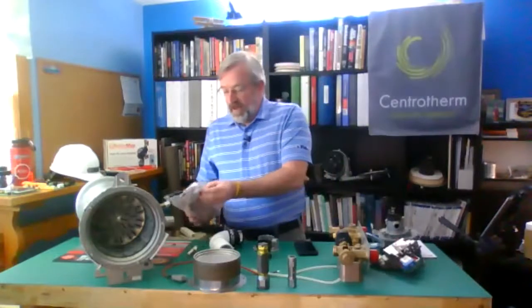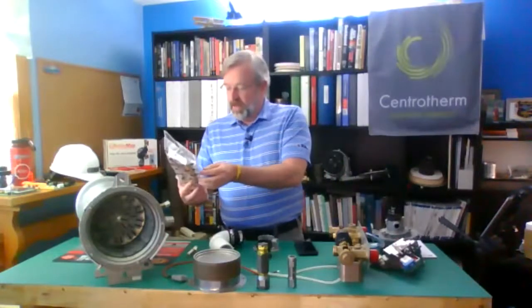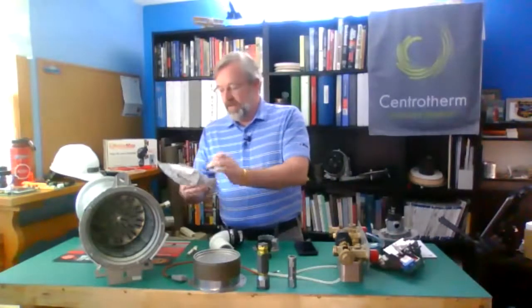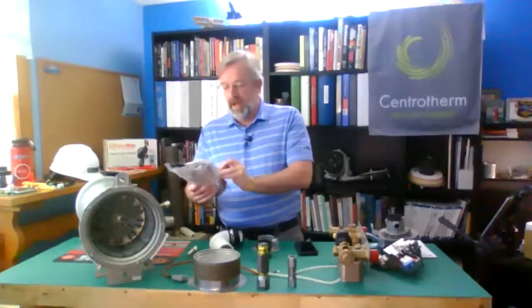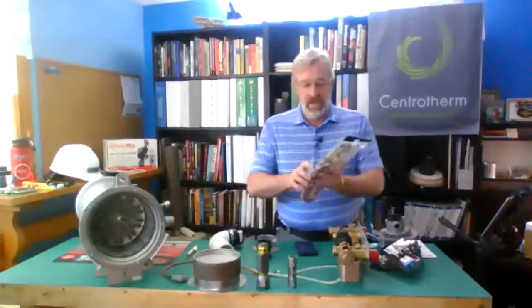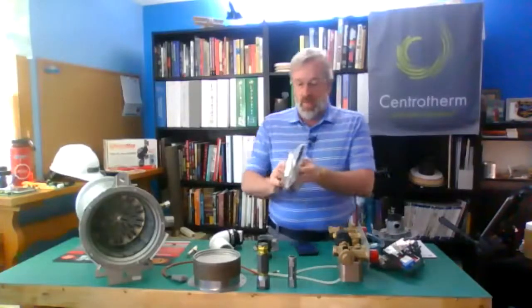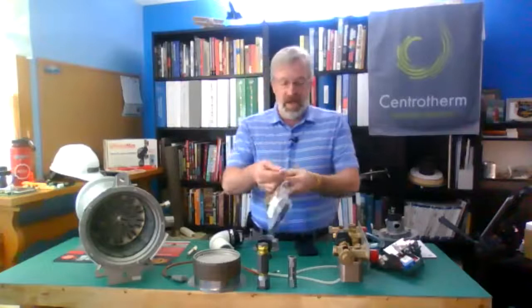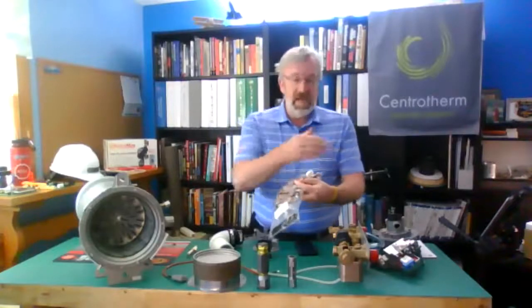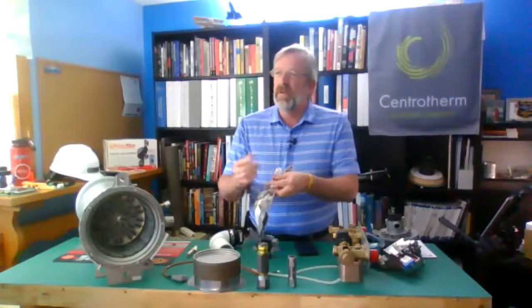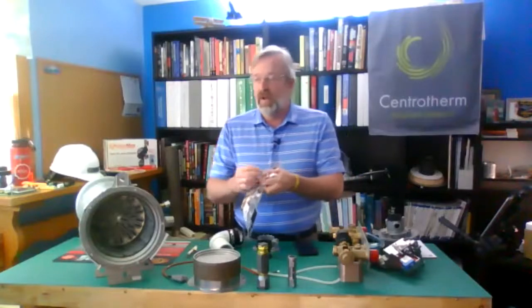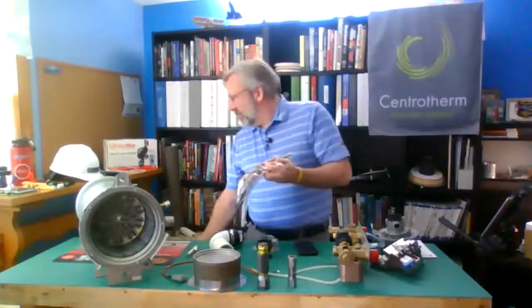Now, the next thing that I might want to check into, let me make sure I get the right end of it here, it's always a challenge, would be the ends of my Molex plug on my gas valve harness. So I do have two separate sides to it, and one side goes down and connects onto my control board. One side connects to my gas valve. We want to check for 24 volts here.